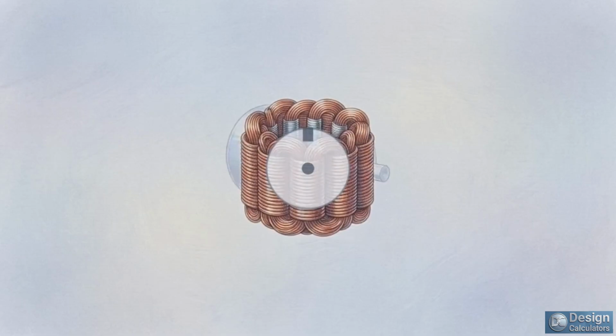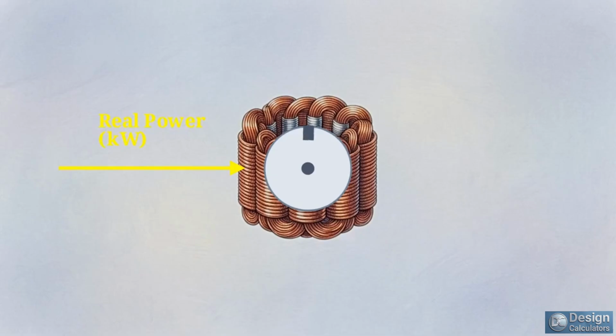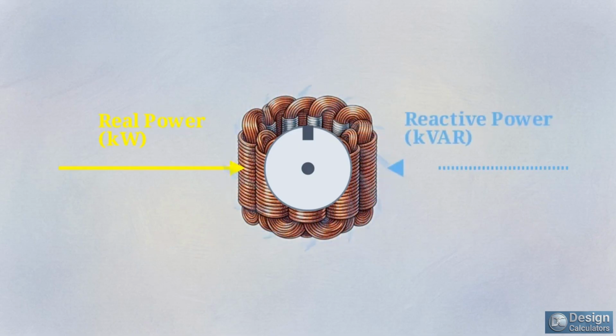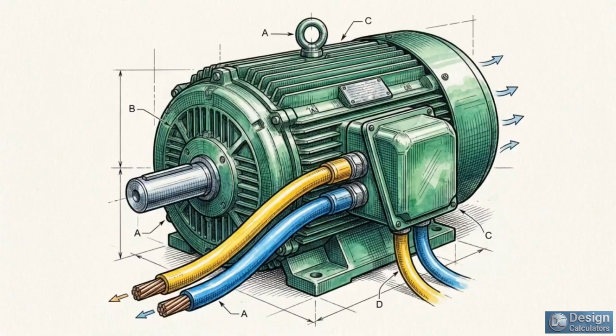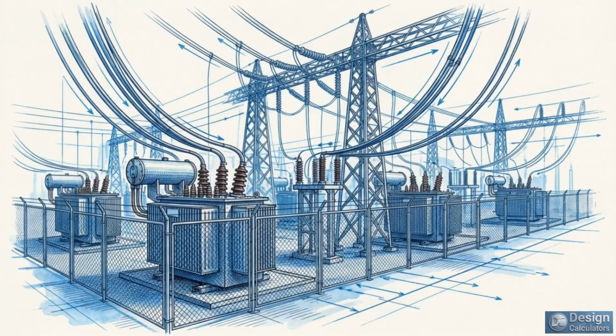To see where power goes, we look inside the motor. The actual energy performing the mechanical work of turning the shaft is real power, measured in kilowatts. But first, the motor must establish a strong magnetic field inside the casing. Sustaining those magnetic fields requires a distinct stream of electrical energy known as reactive power. Therefore, an induction motor inherently demands two different streams of electrical power simultaneously just to function. Adding those two streams together gives you apparent power. This is the total volume of electrical power your physical cables and transformers must carry.